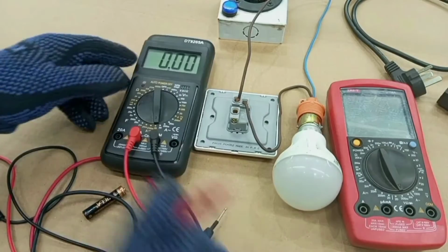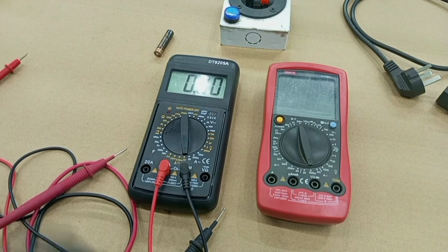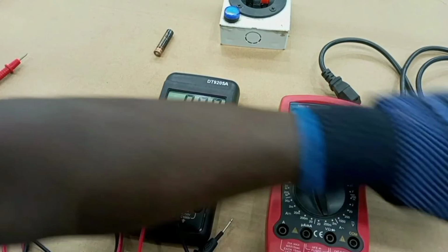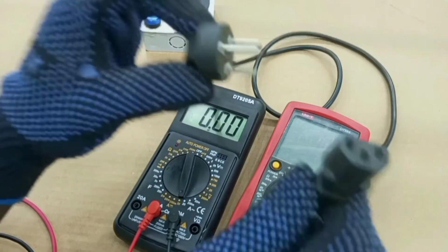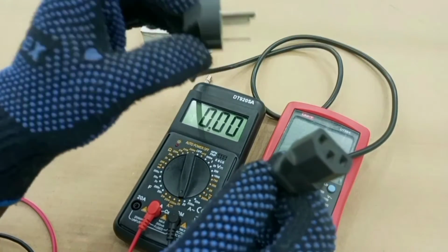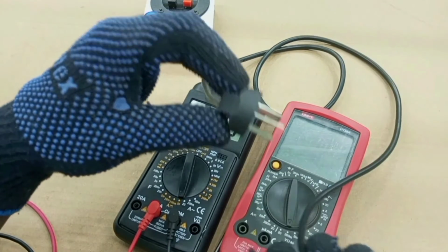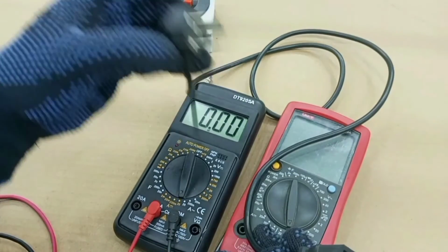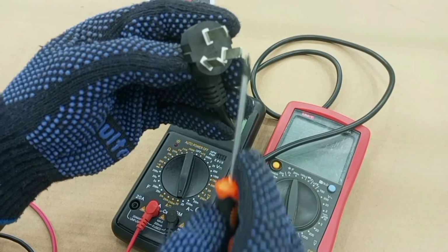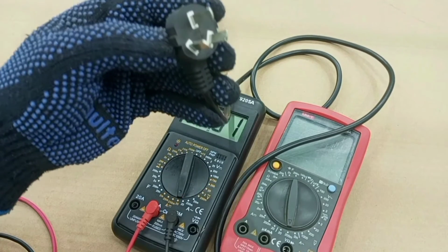Okay. All right, so the next thing we are going to do is actually a test that we can use the multimeter to do, and that is to check for continuity of a conductor. All right, so for instance, you expect this cord to supply power from a certain socket to a certain appliance. Now, when you connect this cord to the appliance, it doesn't work. And so one thing that can make the appliance not work is if there is a break in any of the wires that connect these pins to the appliance.